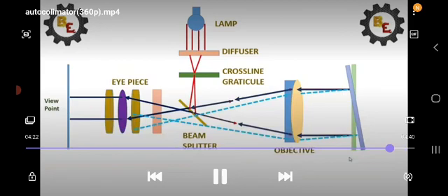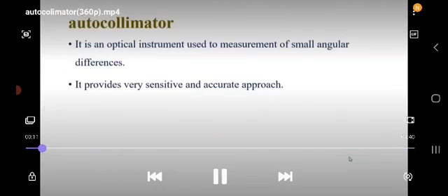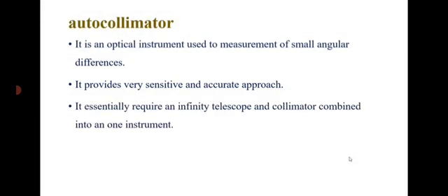It provides a very sensitive and accurate approach for small angular differences. It essentially requires an infinity telescope and collimator combined into one instrument.